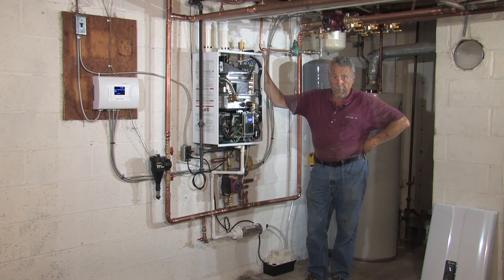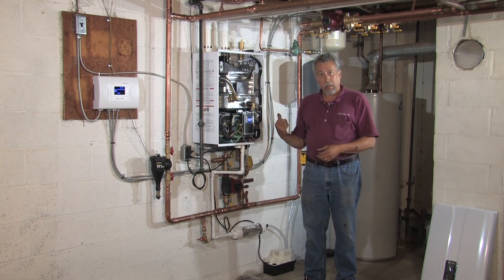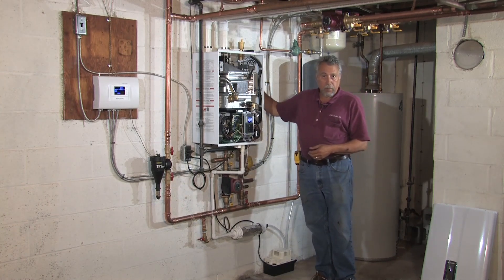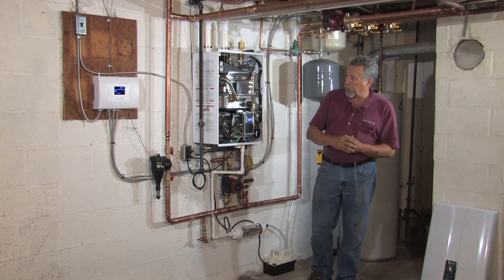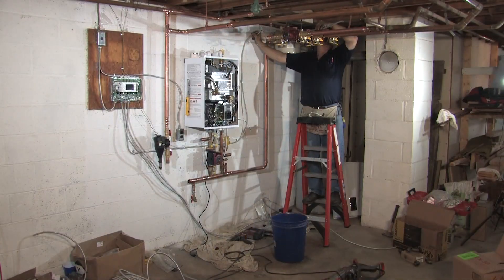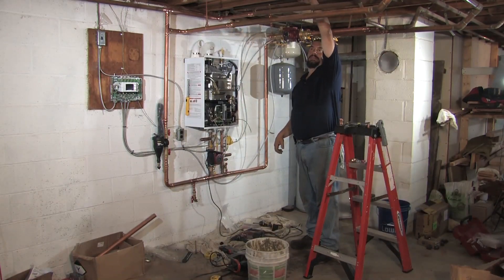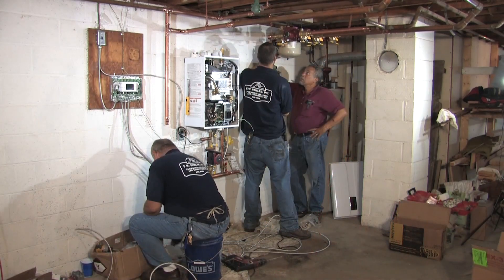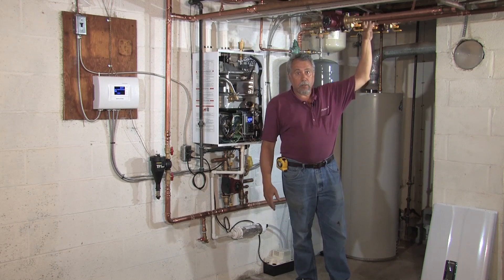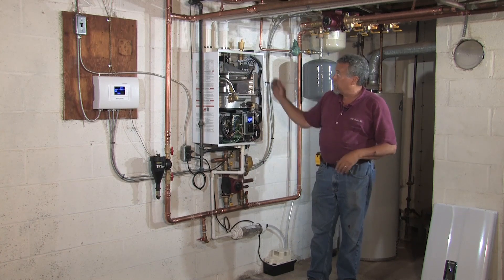This is two thumbs up. Some of the conditions we take into consideration when making this dramatic change from old-style technology to new-style condensing modulating boilers: we look at the floor space we're going to reclaim, which can become storage space. We look for a good solid wall to hang the boiler on, and sometimes that means building a partition. We look at the piping — today we changed the piping from further out in the room, brought it to the back wall, neatened it up, and set ourselves up with a primary-secondary loop. That allows the boiler to see the proper amount of flow through it at all times, and allows our zone circulators to see whatever flow is required. These two circulators don't actually see each other hydraulically, so they operate at whatever speed is required in all instances.